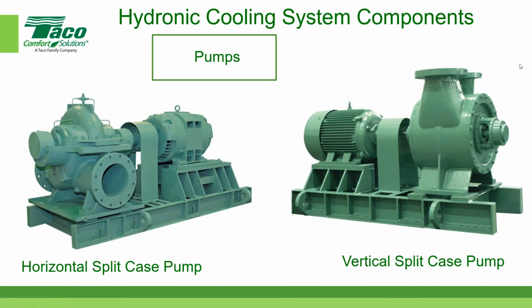Well, let's get my pen again. The horizontal split case is divided along this horizontal plane. You can barely see the division right there and there. That top part comes off in that direction. The piping does not have to be disconnected from the pump in order to service it. If you take the top part of the pump, the casing, off, you can access the bearings, the impeller, the shaft, all kinds of fun stuff.